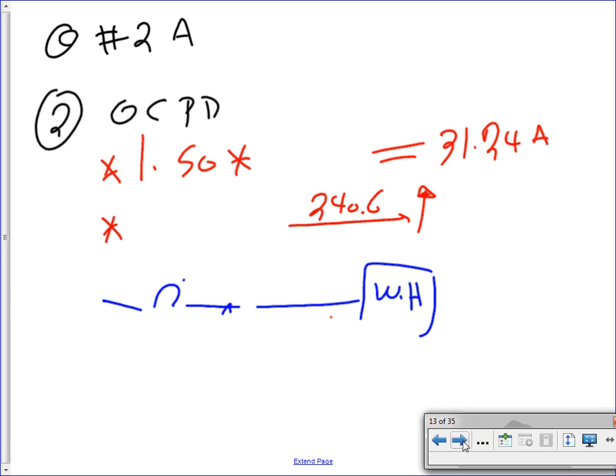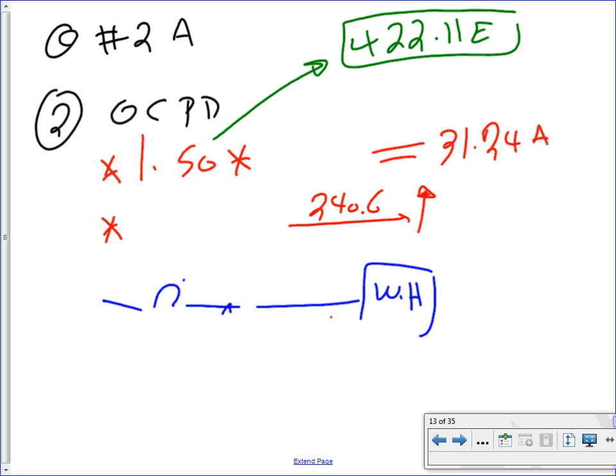Then the second thing, we need to find the overcurrent protection device. I don't know if I have the reference for the overcurrent protection device. For appliances, guys, if your full load amp is more than 13.3, then you can multiply by 1.5. So that's coming from 1.5. This number here is coming from 422.11(E). That's your reference. Because it's a non-motor appliance, no motor in it.